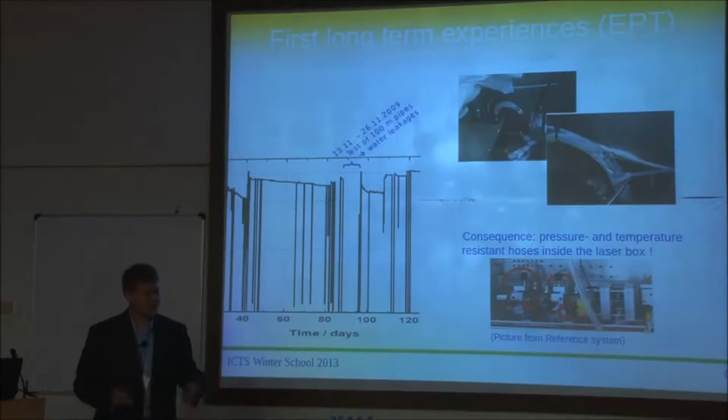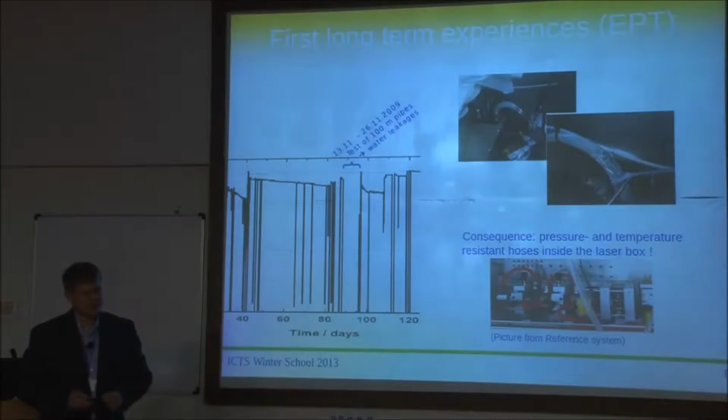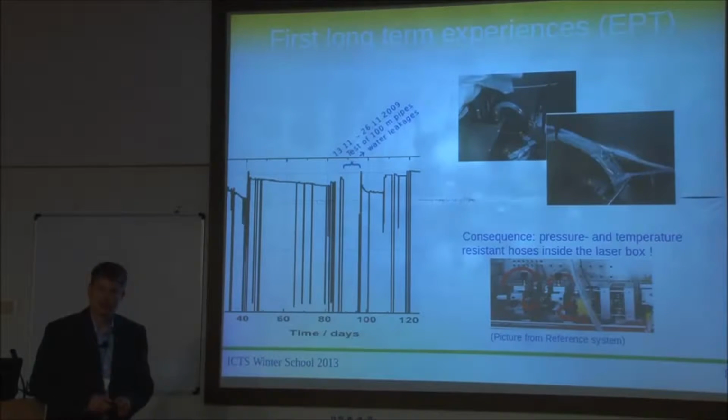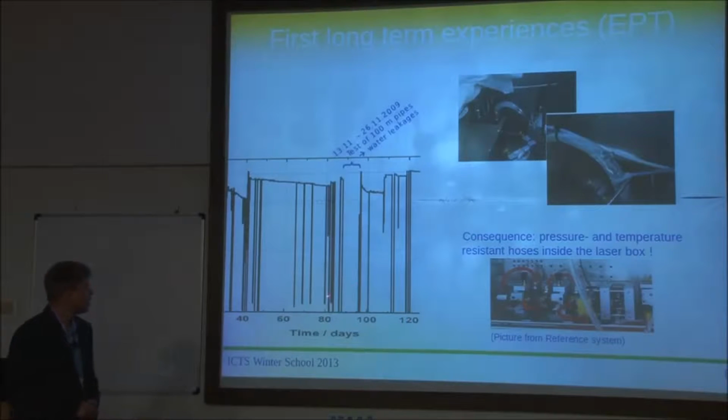So what happened was that all the water was actually flooding the laser box, and that's kind of the worst incident that can happen, because it's really a mess to clean all the optics, all the realignment. We were worried about rust in that laser box, and it took quite a while to fix it. So that's something like 2 weeks or so, and we were really continuously working on fixing that thing here.